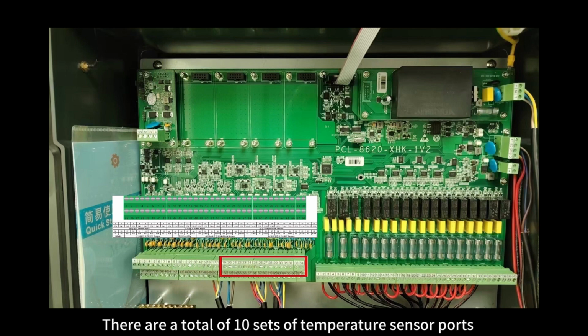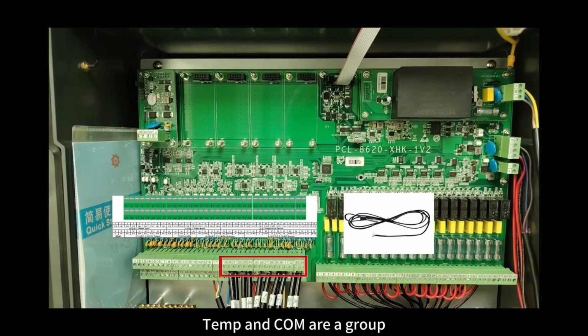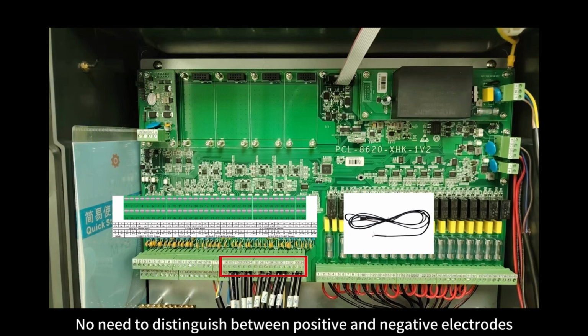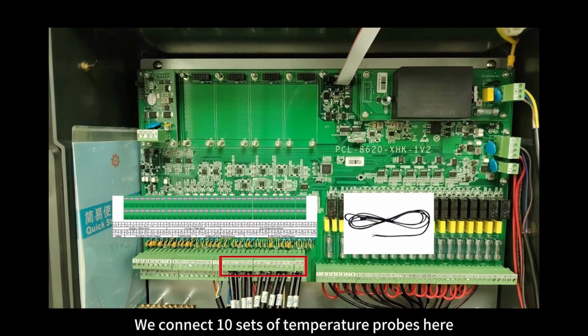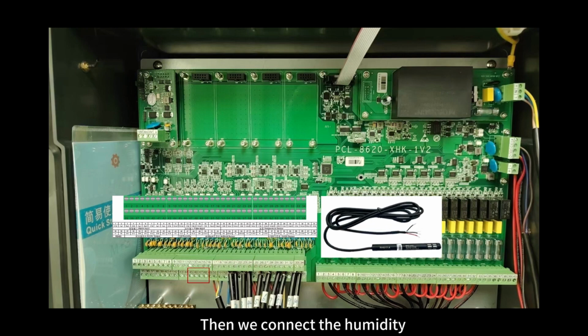There are a total of 10 sets of temperature sensor ports. Temp and COM are grouped. No need to distinguish between positive and negative electrodes. We connect 10 sets of temperature probes. Here, shielding layer grounding. Then we connect the humidity.